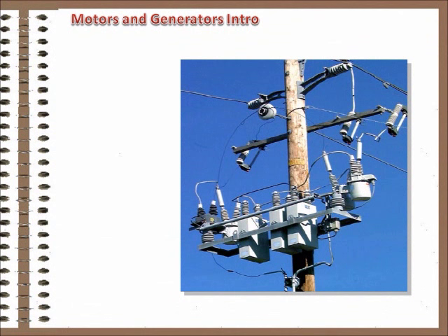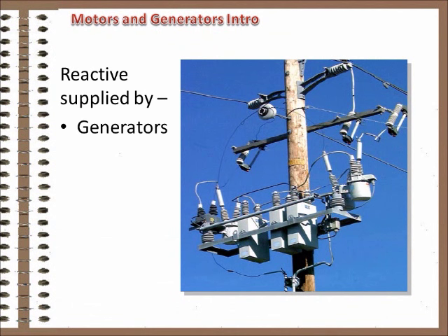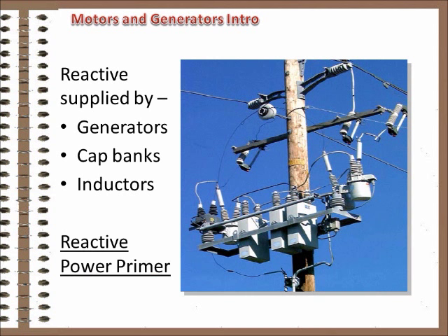The system demands reactive energy, and it either has to be supplied by the connected generators in the form of VAR flow, or modified by the addition of specialized equipment in the system, capacitors or inductors, depending on the nature of the reactive demand. That's the subject of another video in this series, reactive power primer, also available on my YouTube channel. Watch it to get more detail on reactive control.